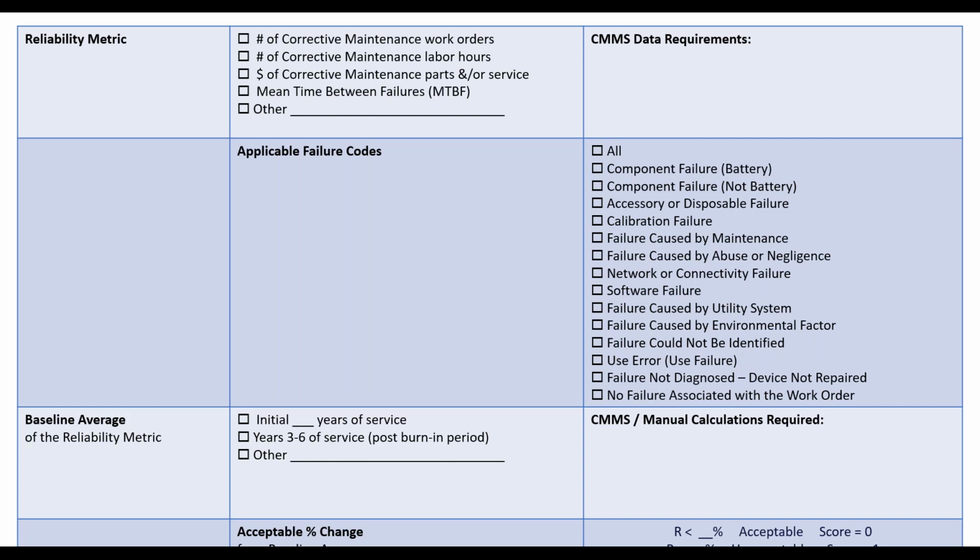And as far as the age of the device, it's aging. However, the manufacturer guarantees parts for another 10 years at this point, so the risk of running out of parts is very low. So gauging the risk tolerance from a business perspective is one of the biggest factors in this, because if you have a team of biomeds that can completely repair machines and parts are available, you can go far out on that. So it'll be interesting to see what other people say about that.